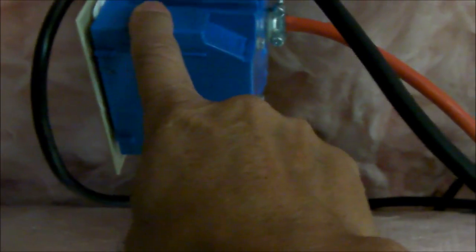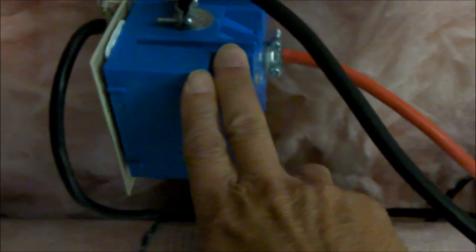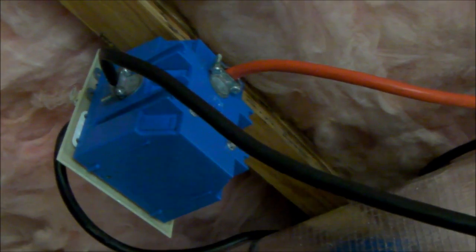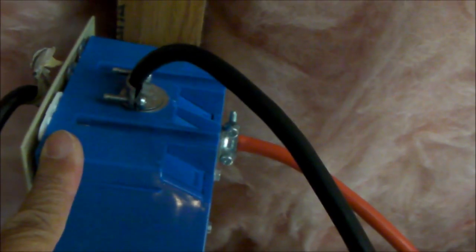The relay that's in this box here is controlling all the power to the motor or all the power to the pump. So you think about it, the relay that's in here is not in a nasty environment. It's not moving up and down. It's not being subjected to a lot of moisture or anything else that's going on in the pit. It's in a nice, clean, controlled environment. And if it's sized properly with a motor horsepower rating, it's going to be quite reliable. So that's it in a nutshell. The float switch controls the contactor or the relay coil. And the power coming off this cord is controlled by the relay contacts and determine whether power is applied to the pump or not applied to the pump.